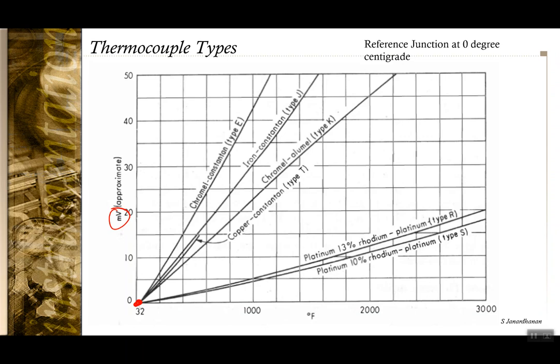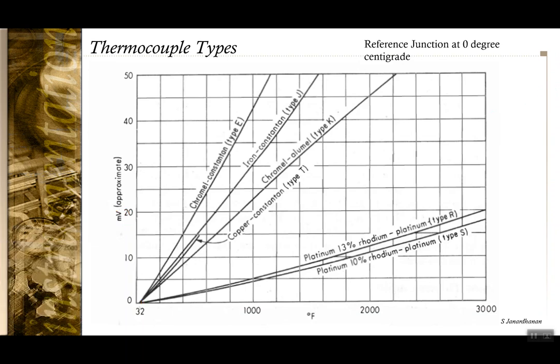Okay, and even though technically a lot of metals are theoretically forming thermocouples, only a few combinations of them have enough linearity in their characteristics to be actually used as thermocouples, and some of those examples have been kept here. Even in this, depending upon factors like cost or temperature range being measured, you have to see which is the appropriate choice of a thermocouple.